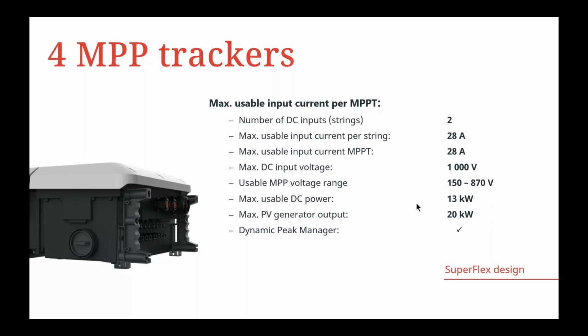The maximum usable DC power for a single MPPT is 13 kilowatts, and the maximum PV generator output power is 20 kilowatts. It also comes with our software design of Dynamic Peak Manager that enhances your PV generation and is always tracking the global maximum power point so the inverter generates maximum power from your solar panels. This brings the Superflex design to the Fronius Verto with multiple integrated MPPTs.